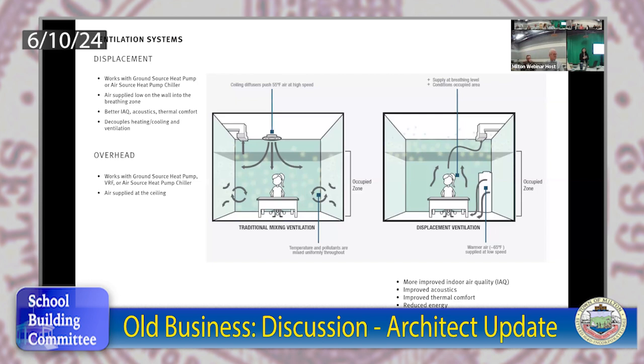So those are the two big things - you will get good air quality, and slightly better air quality with displacement, but the acoustics and thermal comfort are the two biggest components. You'll notice that option 3, the VRF, can't use displacement, and that's just the way that system delivers to the space - it just can't be through displacement. Where options 1 and 2 can do displacement, they can.